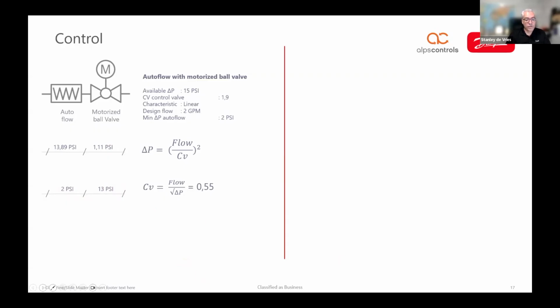And that means that more or less you have already lost 70% of your valve characteristics. So you close it for 70% and then it starts to do something, which is probably not very good for the control, right? Because the control likes predictability. So nothing happens, nothing happens, nothing happens. At some point, something happens, but then your integration time and all those things have gone rather haywire already. So this basically gives you on-off control. So if you put a 0 to 10 volt actuator on this valve and you put a circuit setter before it, you could have just used on-off here because it doesn't really matter much.